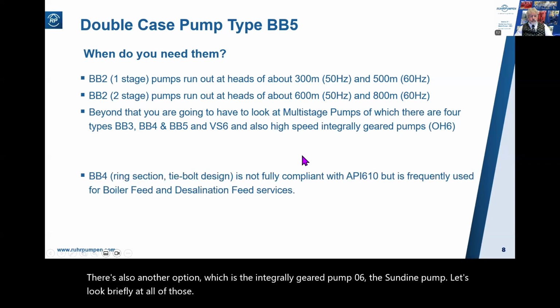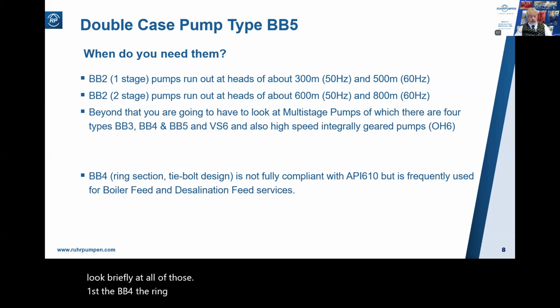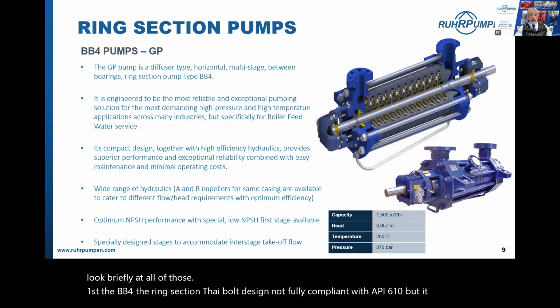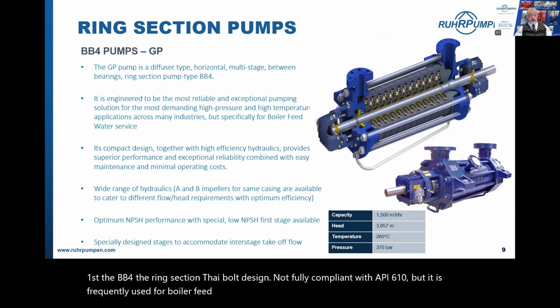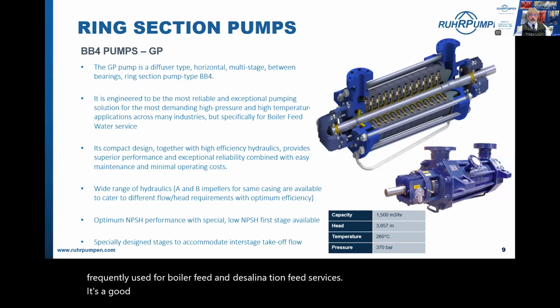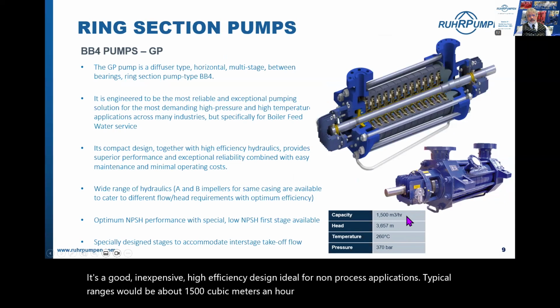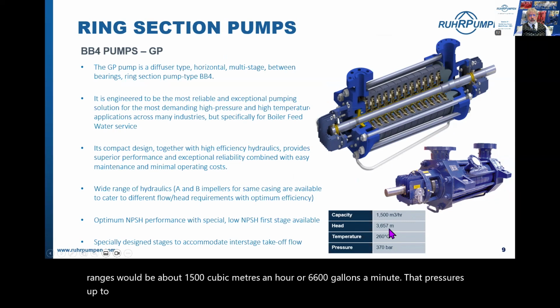First, the BB4, the ring section, tie bolt design, not fully compliant with API 610, but it is frequently used for boiler feed and desalination feed services. It's a good, inexpensive, high efficiency design ideal for non-process applications. Typical ranges would be about 1,500 cubic meters an hour or 6,600 gallons a minute, at pressures up to about 3,700 meters, which is 12,000 feet.